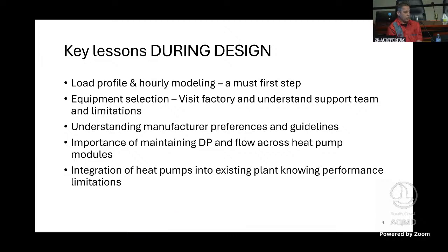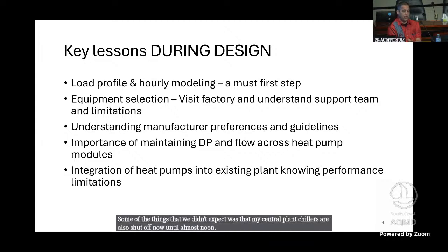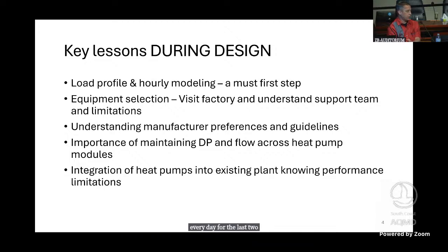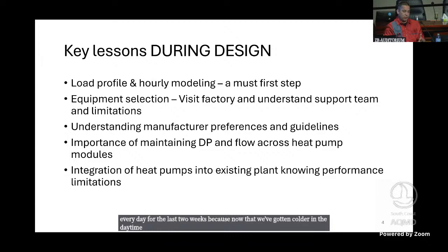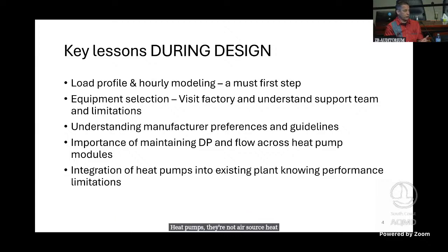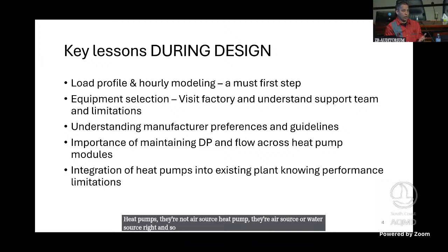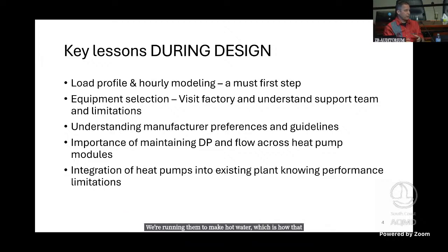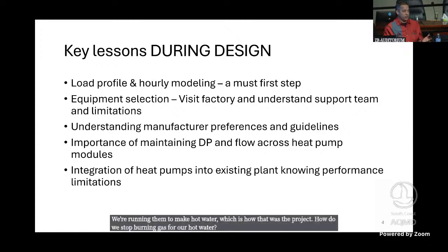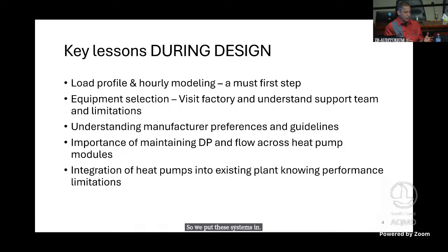And it started up on day one, and it worked. Our boilers have been shut off since July, and every day we're getting smarter on how we run those. Some of the things we didn't expect: my central plant chillers are also shut off now until almost noon every day for the last two weeks, because now that it's gotten colder in the daytime, the heat pumps - they're air source or water source - we're running them to make hot water, which was the project. How do we stop burning gas for our hot water? So we put these systems in to make hot water, that's why we're there. That means any byproduct of that, the chilled water, is free in my mind.